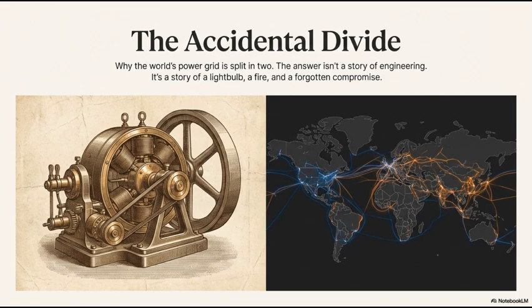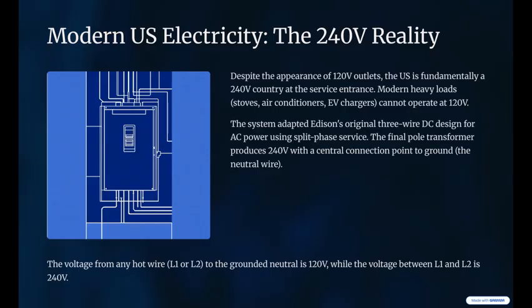Exactly. And the core question we're exploring is really one of prioritized mathematics. Was the U.S. decision to stick with the 120 volt to ground standard, which is enabled by that elegant split-phase system, a mathematically justified compromise? One that's successfully prioritized ground fault safety and managed infrastructure cost over the raw efficiency you get with higher global voltages. My position is that the split-phase design successfully engineered a system that minimizes risk while still providing very efficient 240-volt delivery where you need it.